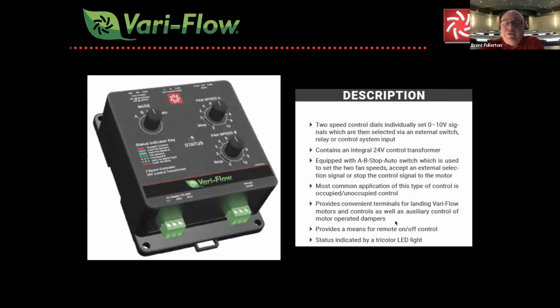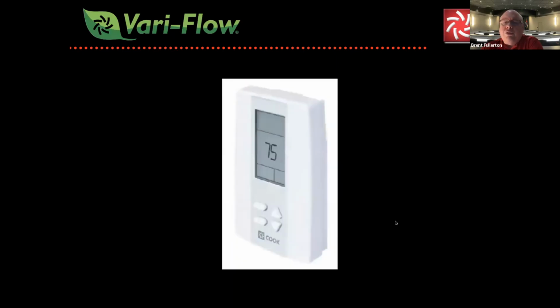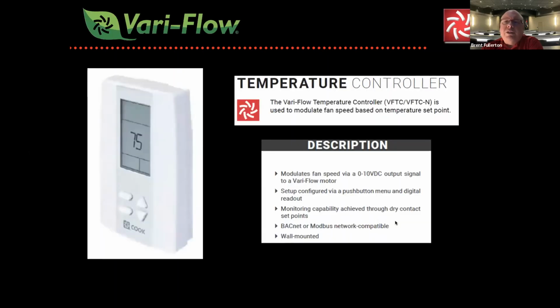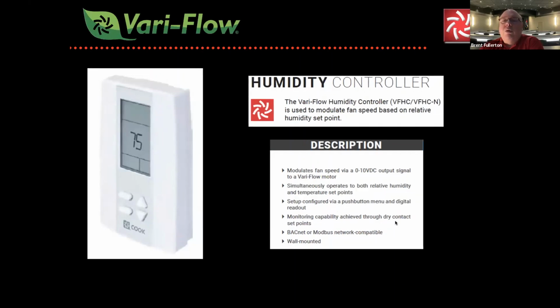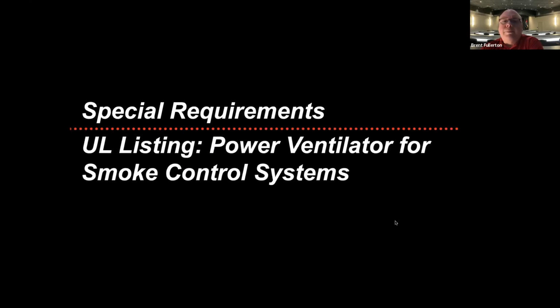Now, very easily, there's simplified controls. You can set whatever you want for the high, whatever you want for the low. And that can be controlled not only by a switch, but it can also be controlled by a control. So what if you wanted to set a temperature range at which it kicks to a higher speed to exhaust more air? Or what if your humidity gets high and you want to tie into that? Now, it can be a standalone or it can tie into a building management system from that standpoint. So all of that are options for controls. Like I said, we did more of a deep dive about last month. I don't want to recreate the wheel, but I do want to highlight and pull that back in.